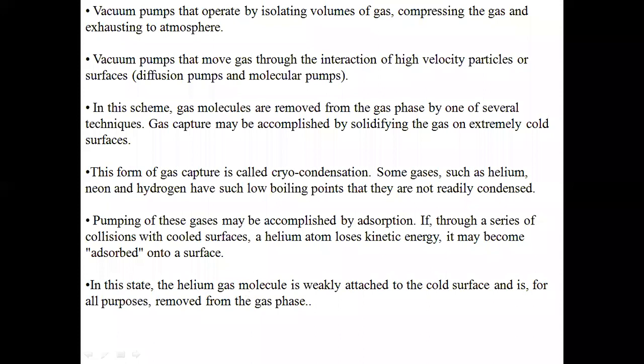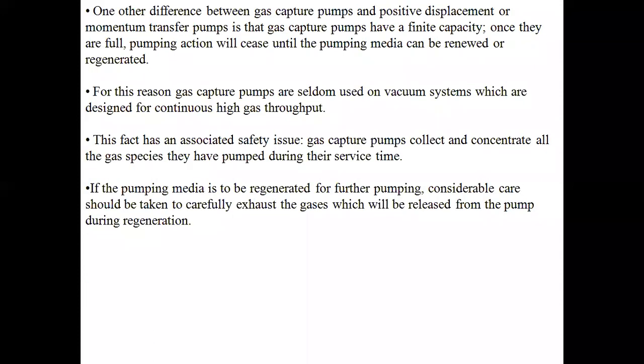Once the adsorbed helium molecules are weakly attached to the cold surface, they are effectively removed from the gas phase. One major difference between gas capture pumps and positive displacement or momentum transfer pumps is that gas capture pumps have a finite capacity — once they are full, pumping action will cease until the pumping media can be renewed or regenerated.